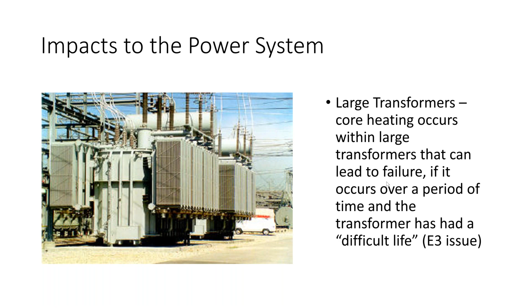Now, I mentioned space weather. The amplitude on an EMP device is likely to be higher than space weather, so that's bad news. The good news is there's so much metal here that to heat that up to a point where it would be a problem does take time. And I mentioned here the fact that if a transformer is old, if a transformer has had very complicated and difficult cycling, if there are maintenance issues involved with the transformer, that the EMP E3 potentially could be the, I'll say, last straw that causes catastrophic failure to the transformer. So we shouldn't ignore that as well. That's another potential out there, although, like I say, to heat the transformer up takes a significant amount of time. John, next slide, please.